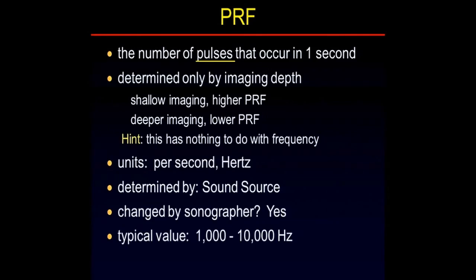So if I happen to have had a piano here and I hit different keys, let's see what it sounds like. Different frequencies, right? But all of these patterns had the same PRF. 3 hertz, 3 pulses per second. How many people get that? Good. Okay. So this is determined by the ultrasound machine, and you can change it. You change it when you change the depth of view.